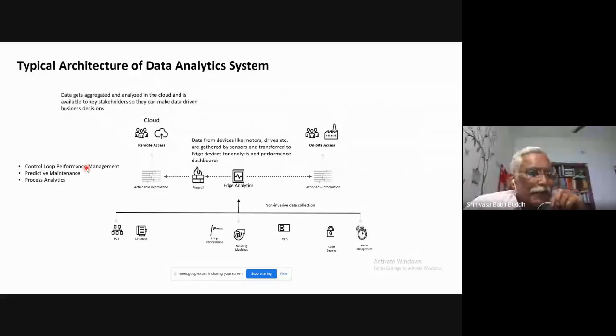Many times what happens is, till recently, people used to follow maintenance practices based on some fixed schedule. Every year in such and such month, you stop the plant and carry out all the maintenance activities. That is really not a very efficient way of doing it. So what people are doing nowadays is, since the data is available from the plants continuously, they make use of that information and are able to predict which equipment requires maintenance. Instead of doing it on a time-based, schedule-based or reactive basis, you can go for predictive maintenance based on condition monitoring and take corrective actions.